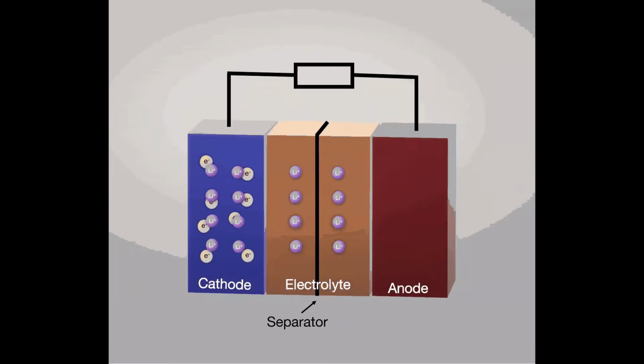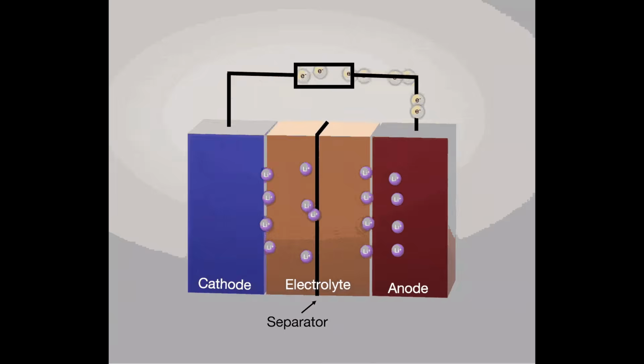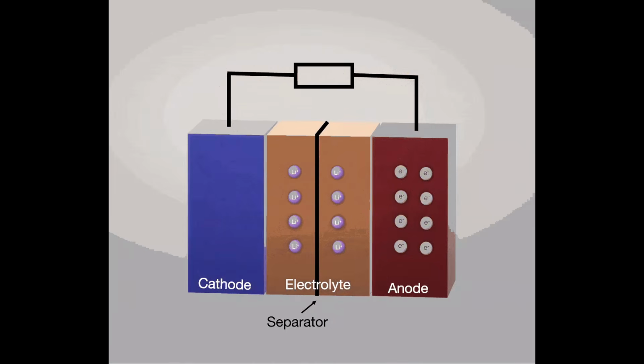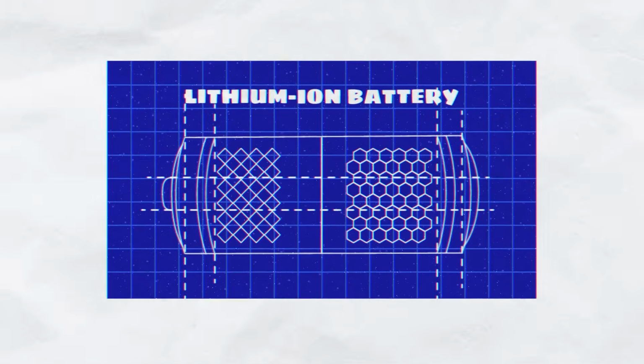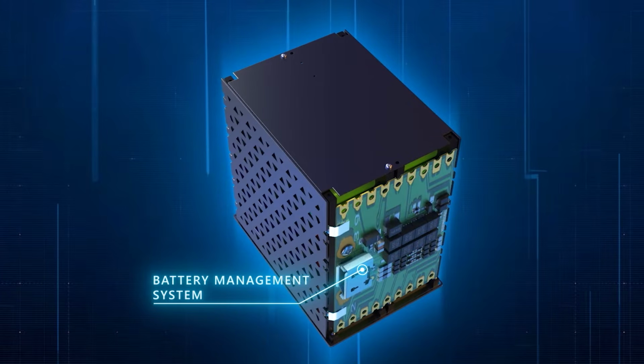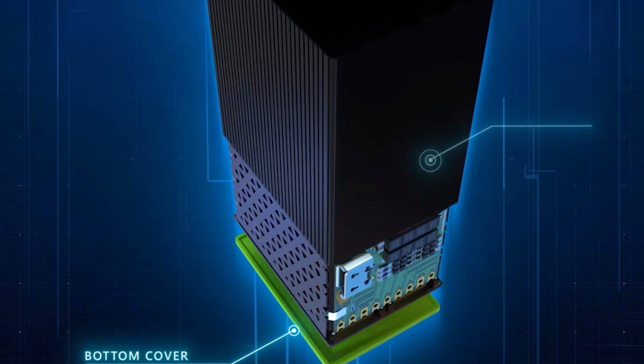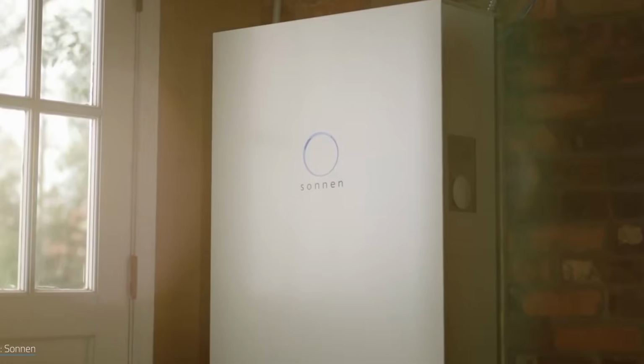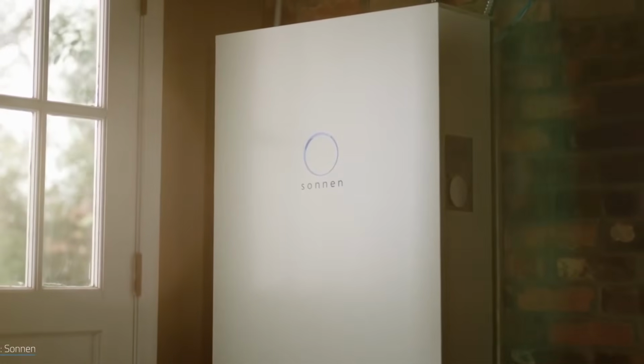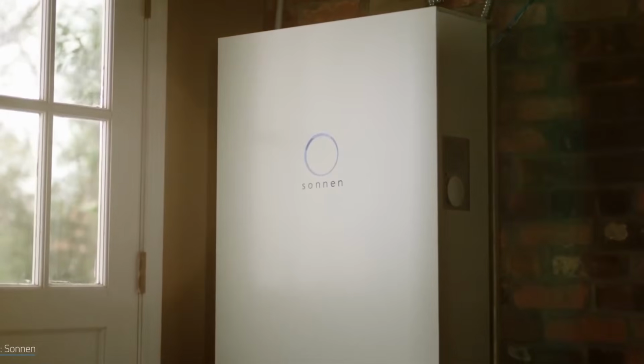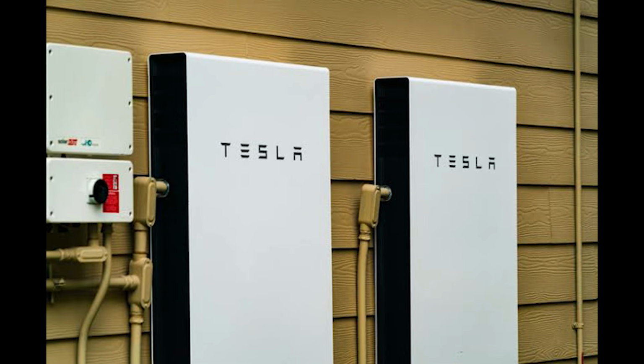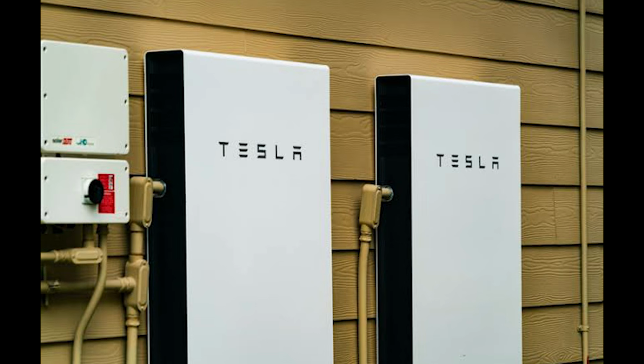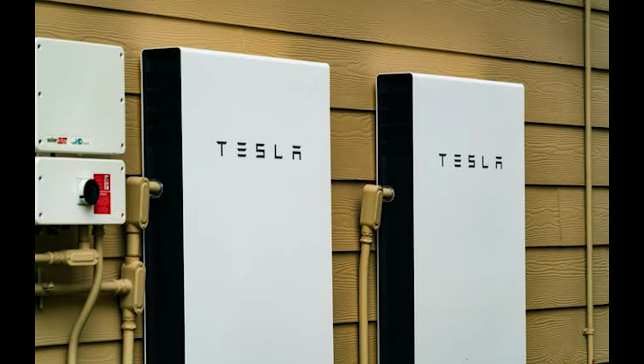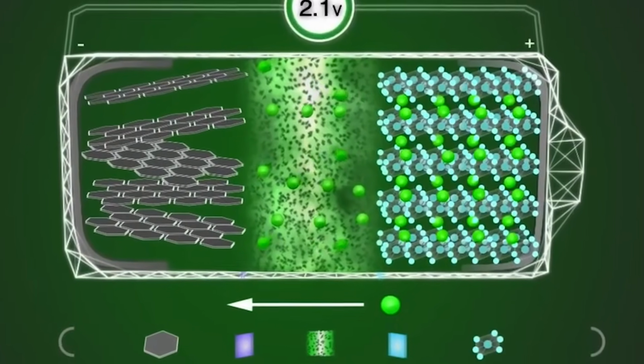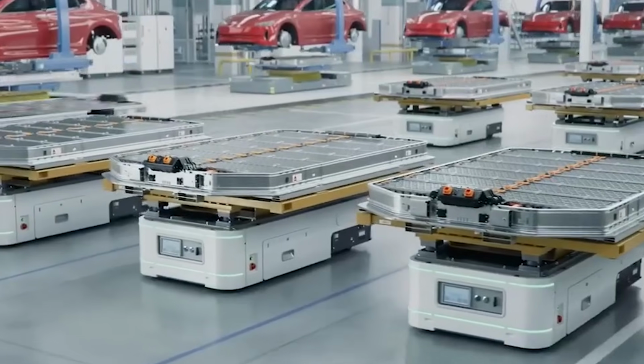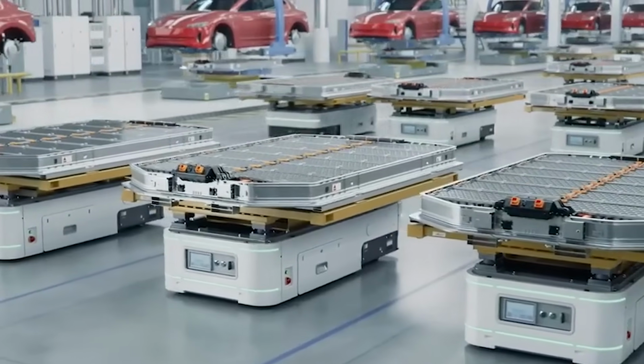Lithium iron phosphate cells start losing discharge capacity below 32 degrees Fahrenheit. By the time you hit -4, most packs are throttled to half their rated output or less. At -20, many shut off entirely to protect themselves from irreversible internal damage. The Tesla Powerwall 2, for example, lists an operating range of -4 to 122 degrees Fahrenheit, and its discharge rate drops significantly toward that lower boundary.